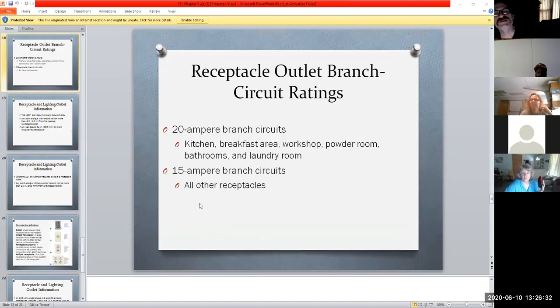Just little considerations, things that they don't normally spell out. You'll see if you look around your house and it's not laid out this way, it's very common. It all depends on who did the wiring, right? But in any case, if we look at our 20 amp delivery, we go up a higher current than our 15 amps that we were using for our lighting circuits, because now we're dealing with little workhorses, if you will. And you'll find that with 20 amp, you're also going to be dealing with a different wire sizing versus your 15 amp. Very commonly for 15 amp circuits, you're going to be dealing with number 14 wire as your pull. 20 amp circuits are going to be pulling number 12.